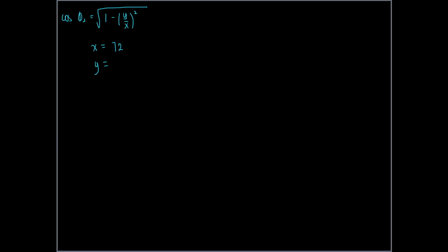So from the problem, we basically have just one working equation for this one. The most economical power factor is equal to the square root of 1 minus (y over x) squared, where y is the charge of the power factor correction equipment per year, given in rupees per kVAR per annum, and x is the charge of the maximum demand per year as well, given in rupees per kVA. That was shown in the derivation in your module. So I hope you've read your module already.